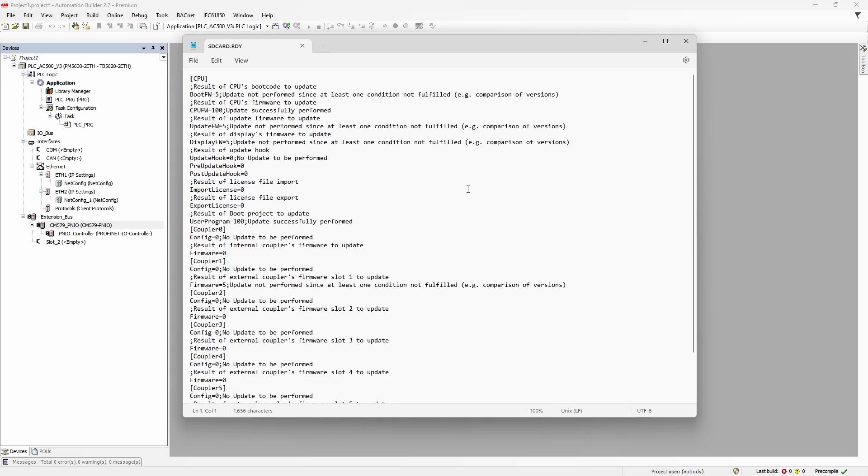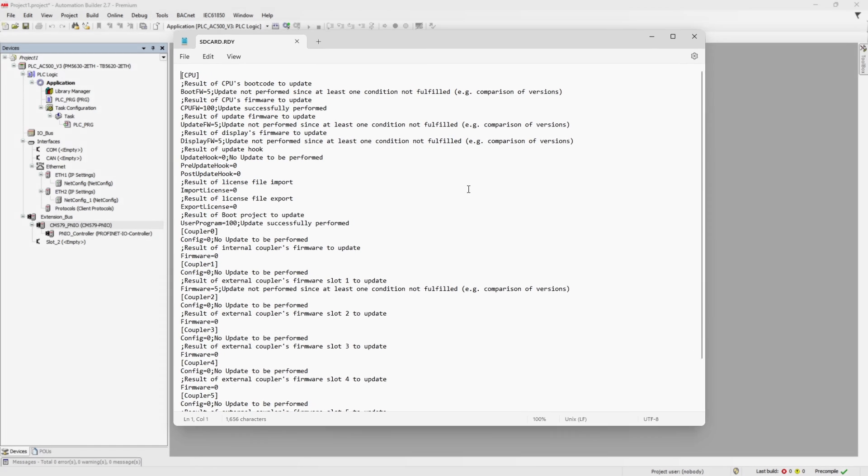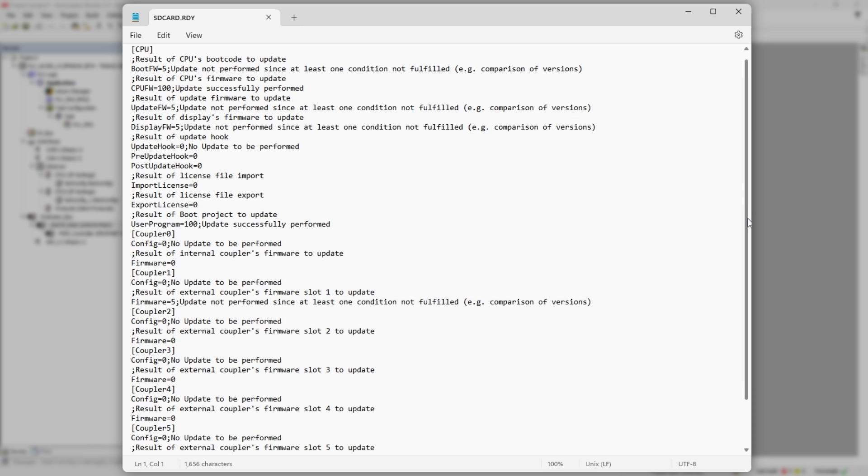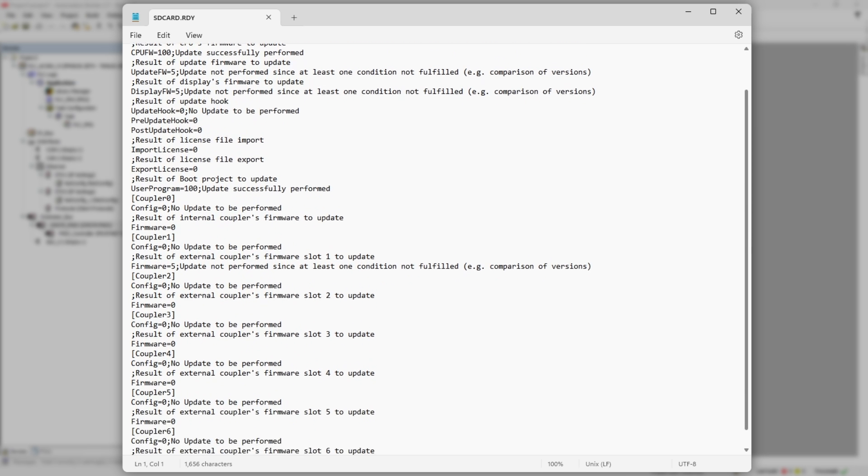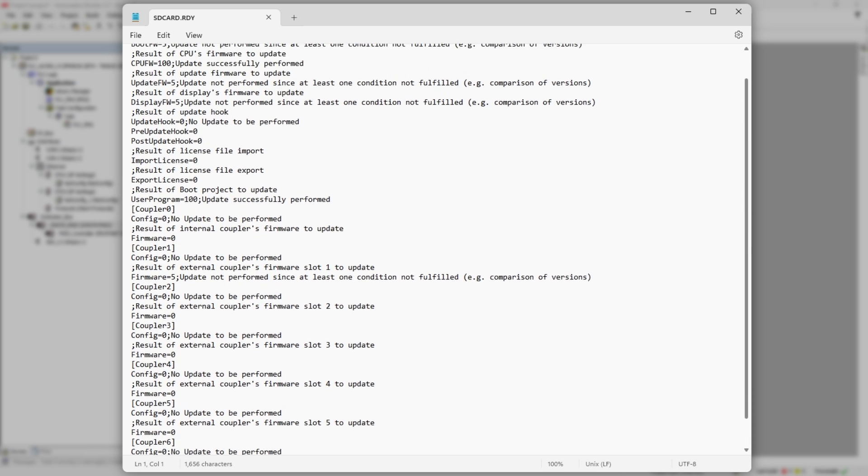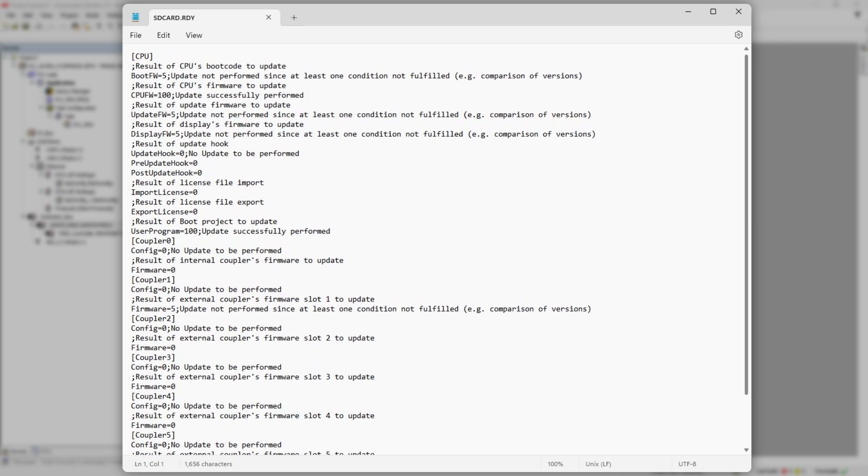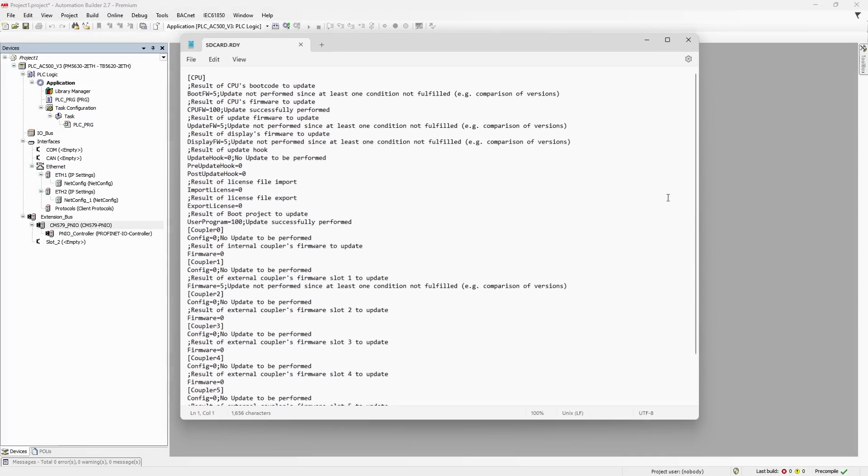After update process is finished, in the root folder of memory card PLC will create SD card RDY file, which is basically log file of update operations. You might want to examine it and check which components were updated, which were not, and what's the reason.